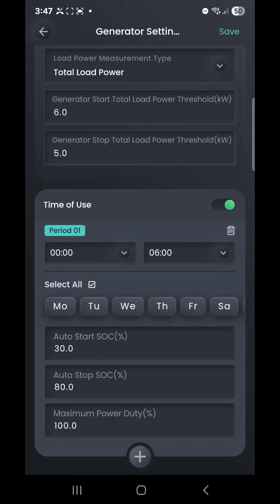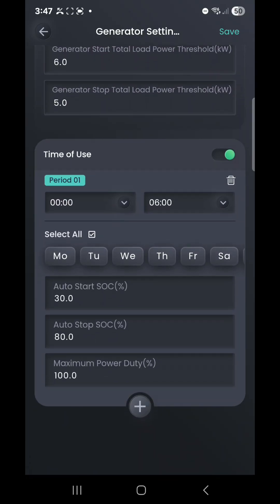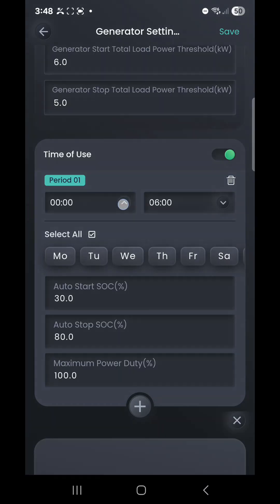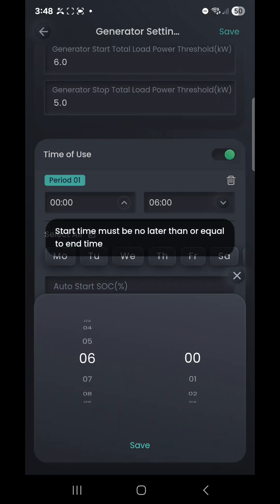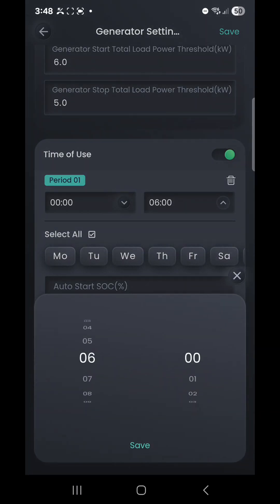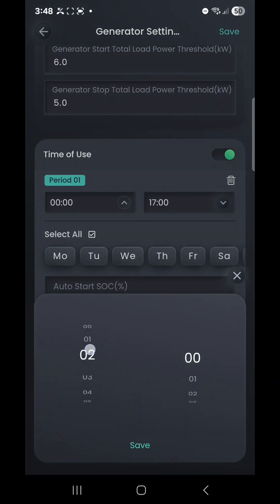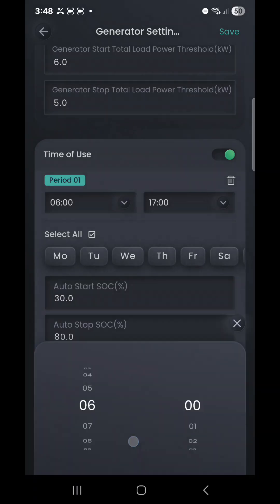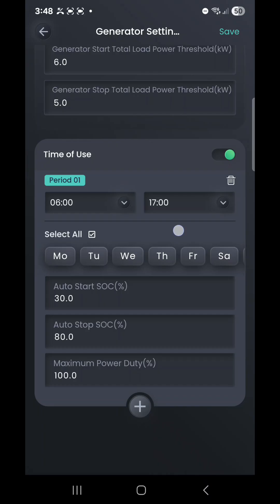We've got our time-of-use controls down here, which essentially let you control when that generator can start and stop. You can say, for example, we only ever want the generator to be able to run from, say, 6 a.m. in the morning. We'll bump this forward to let the generator run up to, say, 1700, and then we can change this to 6 a.m. in the morning. What that means is the generator won't be able to run in the early hours in the morning and wake up the family. That's a pretty cool setting you can set, and we can also select if we want that to be Monday through Sunday by simply sliding that menu, selecting All, or ticking partial days.